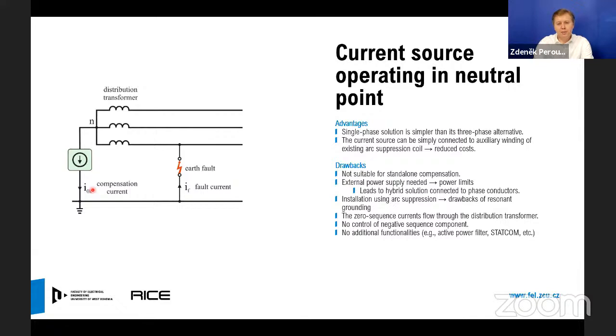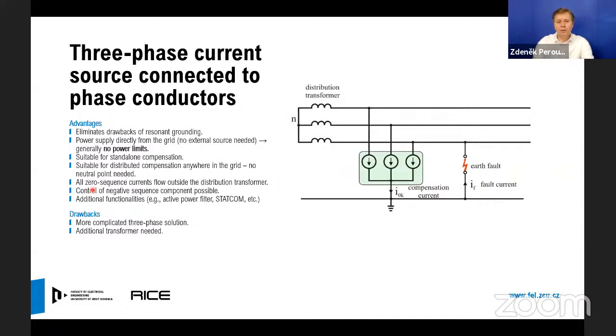Moreover, the installation using the auxiliary winding of the arc suppression coil leads to the same problems with the resonant grounding. So we did not overcome one of the problems of the passive compensation of the fault current. The zero sequence current still flows through the transformer, obviously, and there is no possibility to control the negative sequence component. And of course, we are unable to provide the grid with the additional functionalities which the alternative solution can offer. Therefore, we built the final prototype in this configuration.